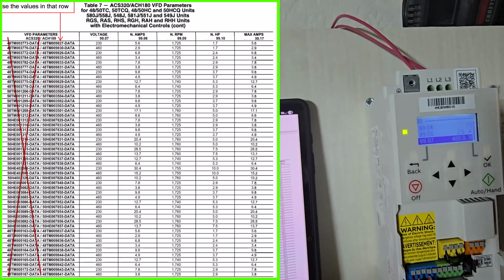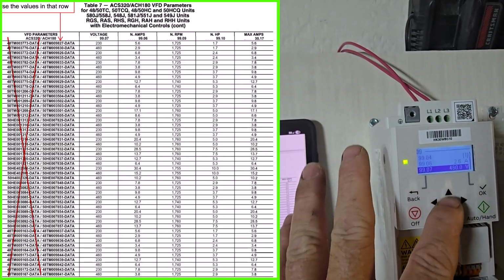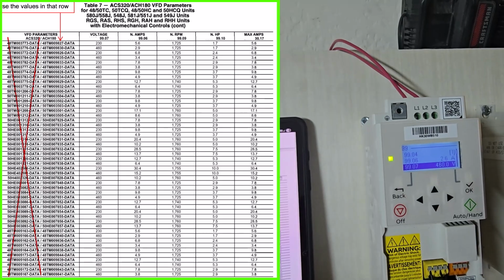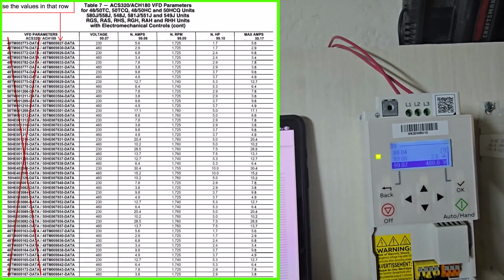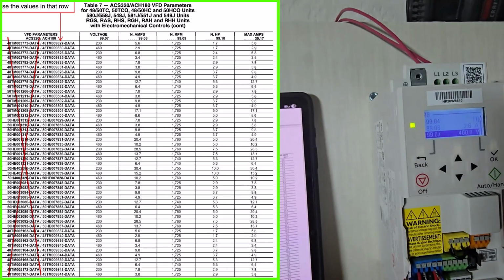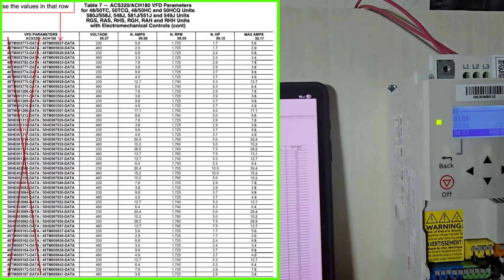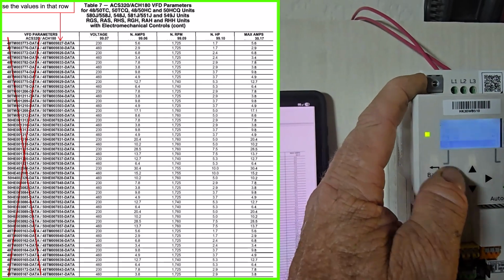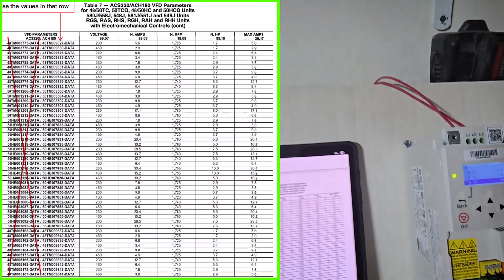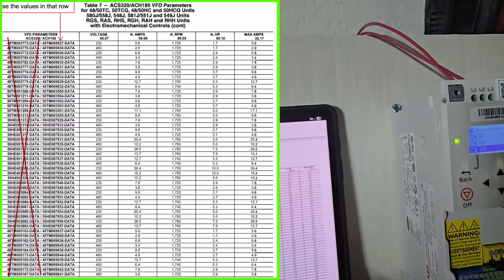It's pretty crazy. So if you enter in the actual site voltage, the nominal voltage there, then it kind of scales your limits based on that. If you leave it at 460, you're probably going to be okay, but that was what we were instructed to do. So that one I'm going to leave for here. I'm using a step-up power supply from 115 at my house to get this for you.